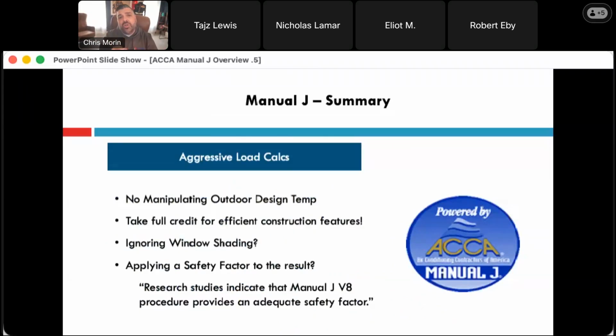Key here is make sure you do an aggressive load calculation, which means you don't manipulate outdoor or indoor design conditions. Always take full credit for efficient construction features like overhangs. When you build a house in Austin, there's a lot of homes that have large overhangs to provide significant shading, which reduces the cooling gain. If your overhang has at least a 2-to-1 ratio above the window—coming out 2 feet and only 1 foot above the window or more—then you're going to include that overhang on that fenestration, because it could significantly reduce the load by 1 to 2 tons sometimes.